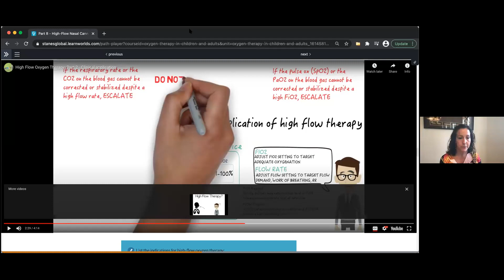As we talked about before, there is a small amount of dead space washout that happens with the high flow devices. And so that can help eliminate some carbon dioxide and contribute a little bit to correction of PCO2, but it's not the most targeted therapy. In order to treat hypercarbic respiratory failure, which is ventilatory failure, you really need to have a different device.